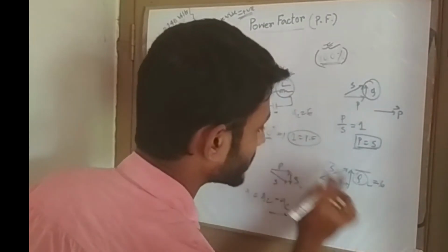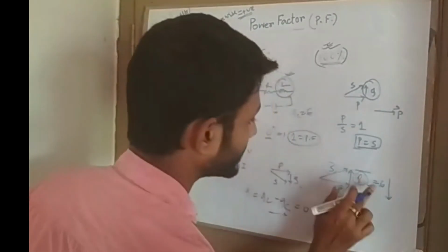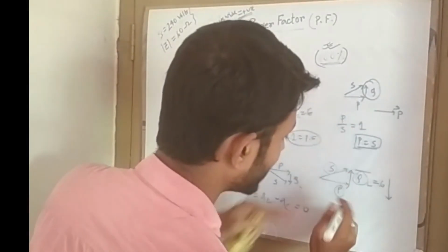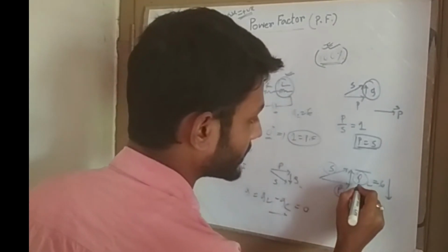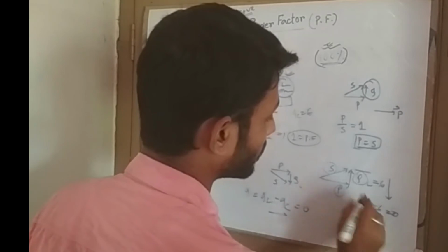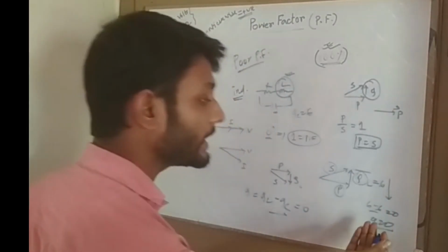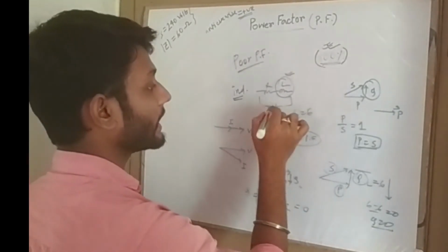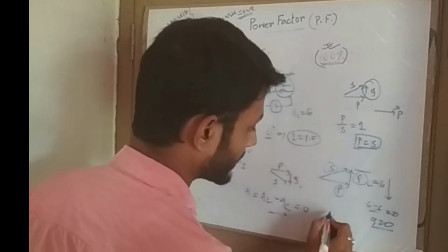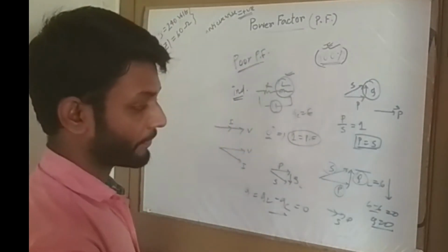So this QC will bring this QL downward. This is plus 6 and this is minus 6. So the resultant, what we can see is QL minus QC, 6 minus 6, it will be 0. Then the Q value will be automatically neglected by this capacitor, then P value and S value both will be same.